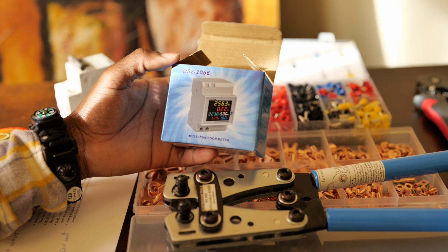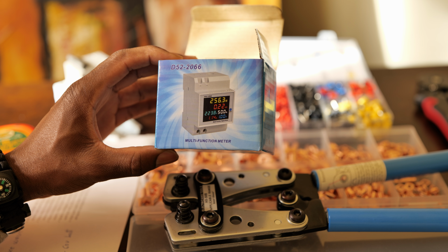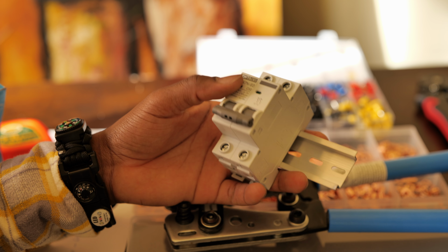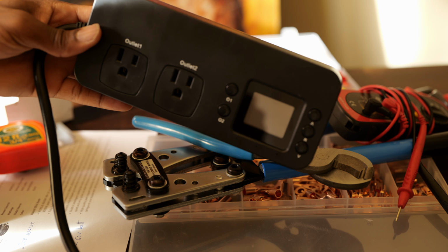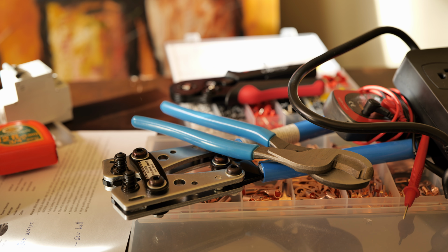To get this set up and tested, I have this multifunction energy meter and tester. It has a display and shows energy consumption information, more on that in a second. This is what it looks like. I also have a circuit breaker, very useful for our setup. I have ferrules to ensure good connection onto the sockets, a crimp tool for the ferrules, lugs, a crimper for the lugs, AC and DC multimeters, and an extension with a built-in energy meter. It's very important to use the right tools for this because we are dealing with high voltage.